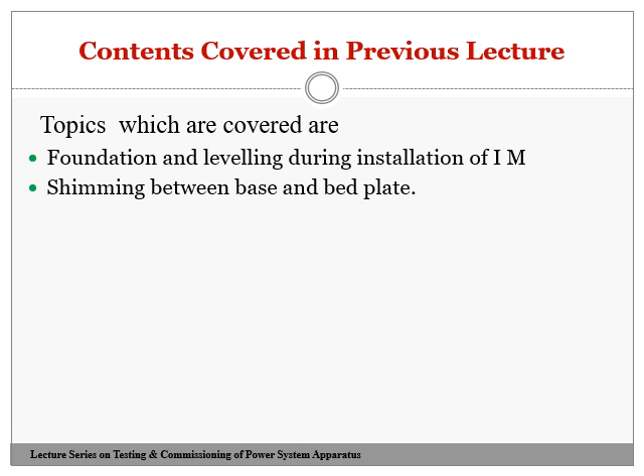In the previous session, we had the topics related to an induction motor, that is the foundation and leveling of an induction motor during the installation. Compared to the transformer, we gave much importance to the foundation requirement for an induction motor because of its rotational movement. It will be operating, depending upon the design condition, maybe at 1500 RPM or maybe 3000 RPM, hence vibration gets caused in the motor. These vibrations should not be passed on to the other machines or the surrounding walls if these induction motors are installed indoor. That's why we provide a foundation.